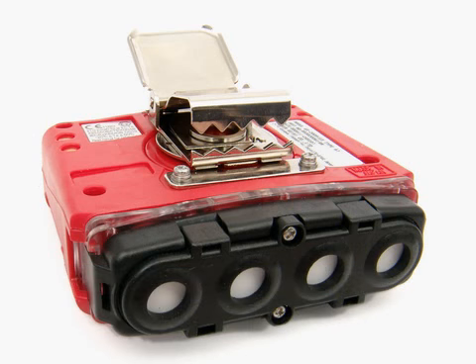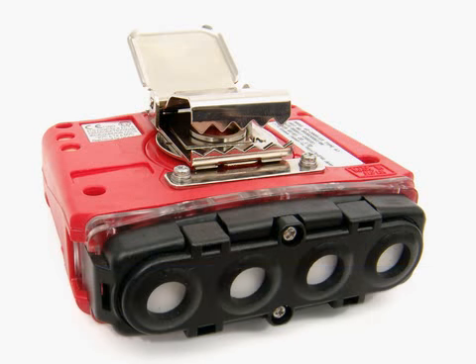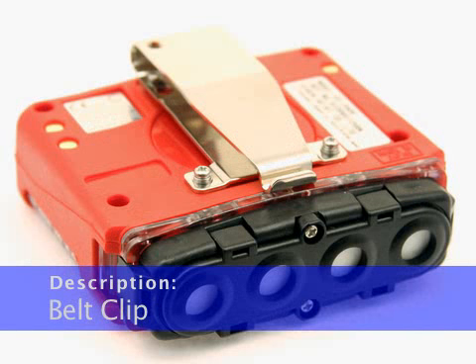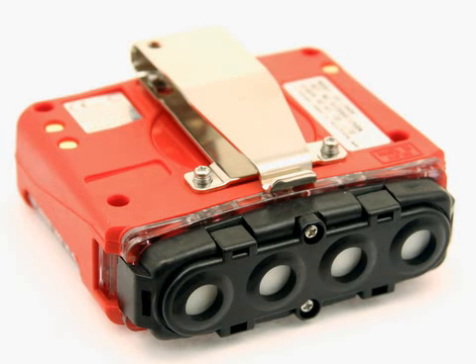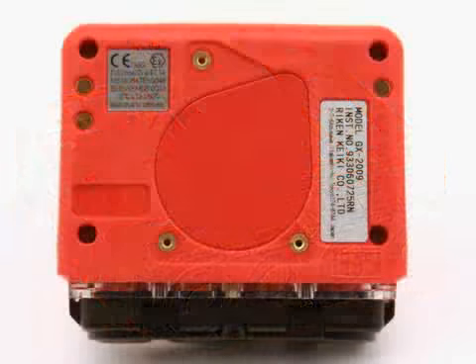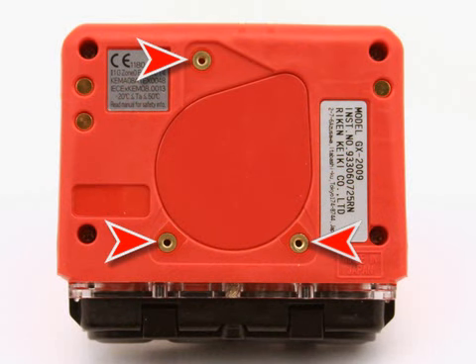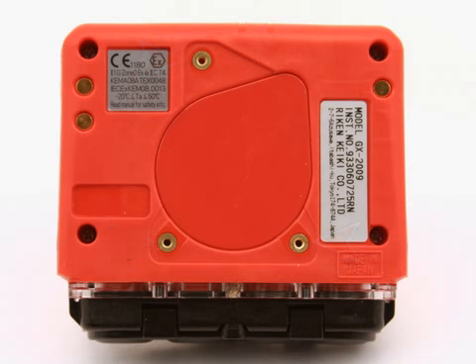The GX-2009 is available with 2 types of clips, the standard alligator clip and the optional belt clip. The alligator clip can be used to attach the GX-2009 to clothing or a belt. The alligator clip can be rotated to change how the instrument is oriented when worn, and the teeth in the clip's jaws prevent the unit from slipping off. The belt clip is used to easily clip the GX-2009 on a belt. There are 3 threaded inserts on the back of the case. These are used to mount the alligator clip or the optional belt clip.